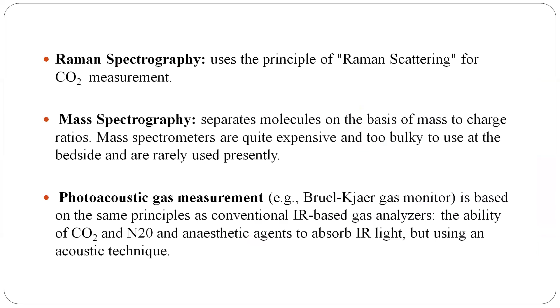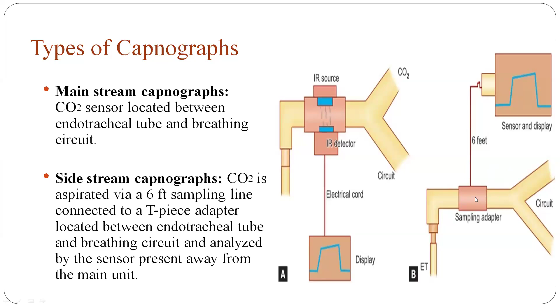There are 2 types of capnographs, that is, mainstream capnograph and side stream capnograph. Picture A shows the mainstream capnograph. In this, the CO2 sensor is located between the endotracheal tube and the breathing circuit, whereas image B shows the side stream capnograph. In this, the CO2 sensor is placed away from the breathing circuit through a 6 feet sampling line, and the sampling adapter will be present between the endotracheal tube and the breathing circuit.